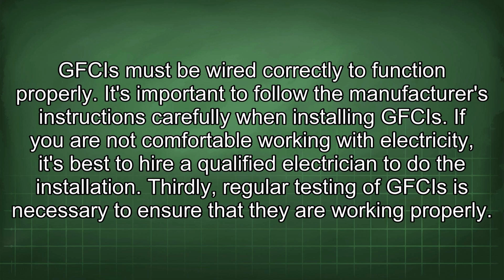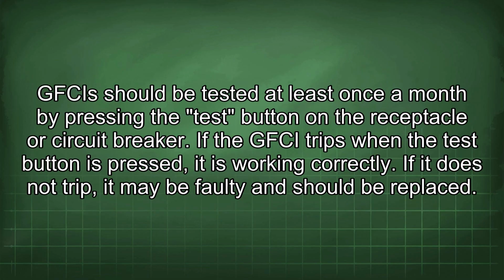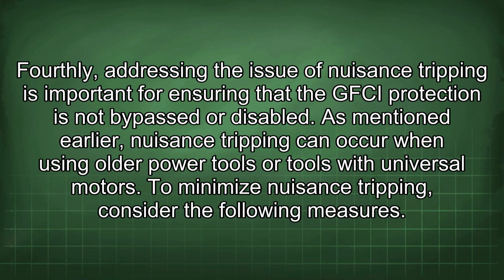Thirdly, regular testing of GFCIs is necessary to ensure that they are working properly. GFCIs should be tested at least once a month by pressing the test button on the receptacle or circuit breaker. If the GFCI trips when the test button is pressed, it is working correctly. If it does not trip, it may be faulty and should be replaced. Fourthly, addressing the issue of nuisance tripping is important for ensuring that the GFCI protection is not bypassed or disabled.